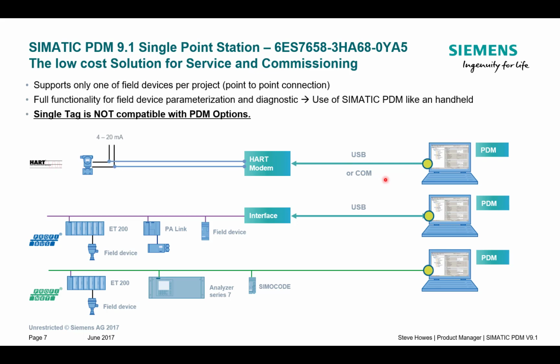What we're talking about is single point - talking to one instrument at one moment in time. If I want to talk to another instrument, I need to create another project. So we'll have a look at this here. We can see that I'm communicating on HART, Profibus and Profinet, but I'm only talking to one instrument on that network. If I want to communicate to another instrument, let's have a look what we have to do.